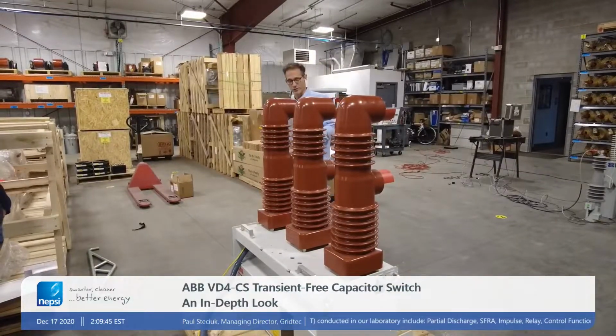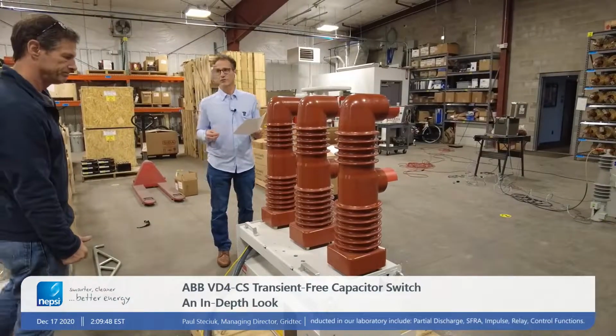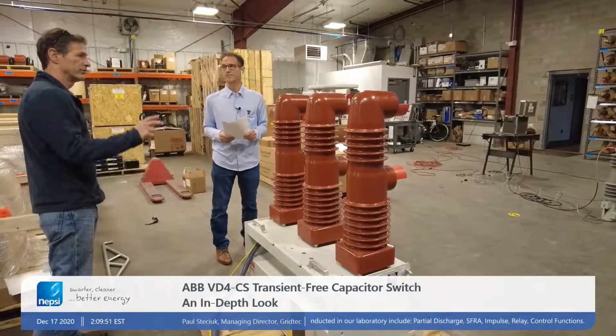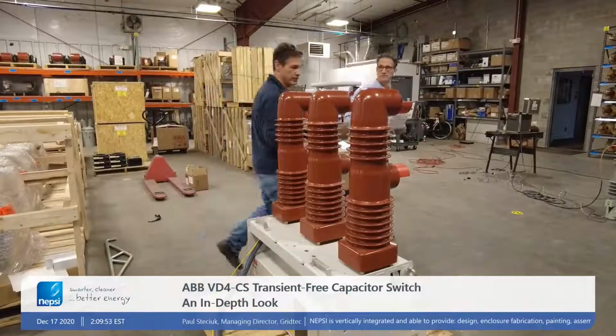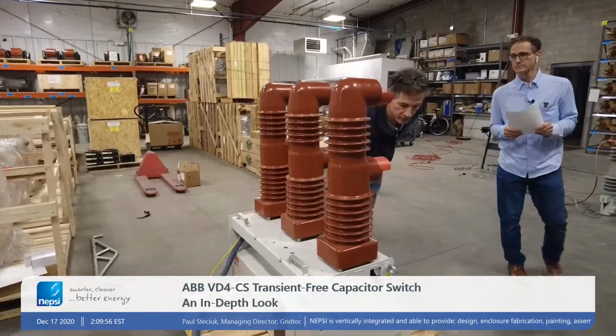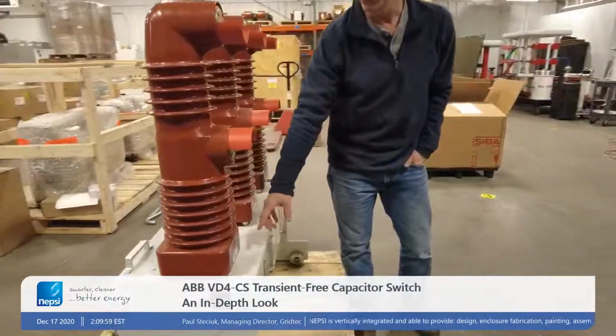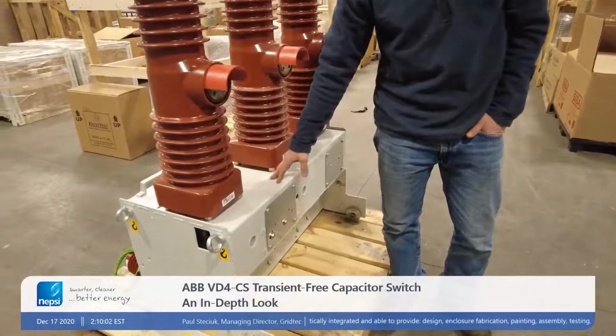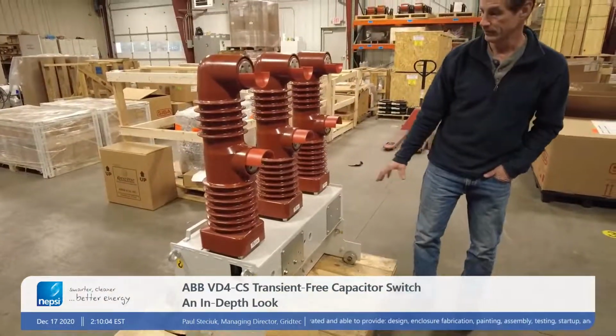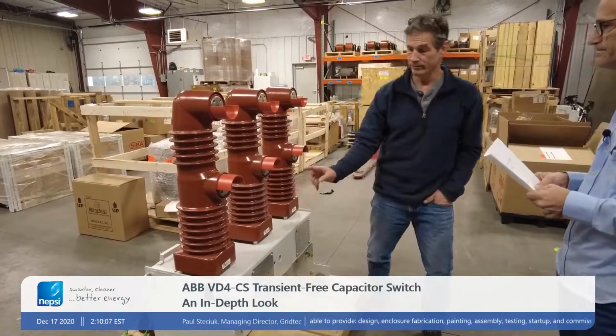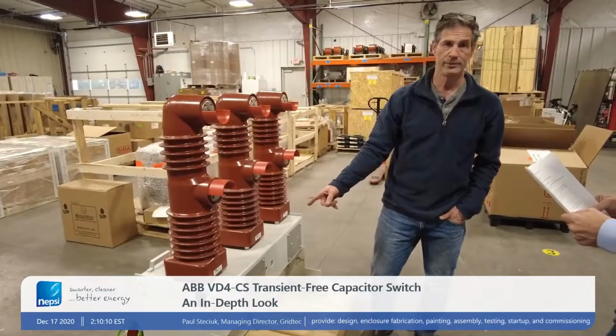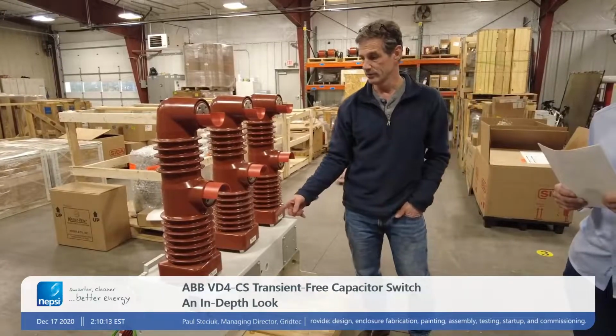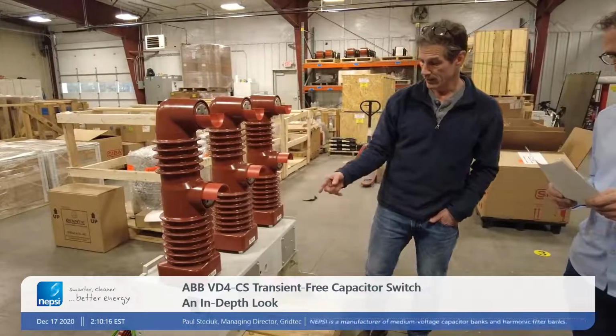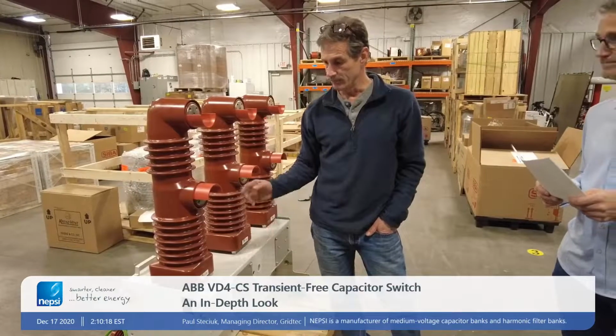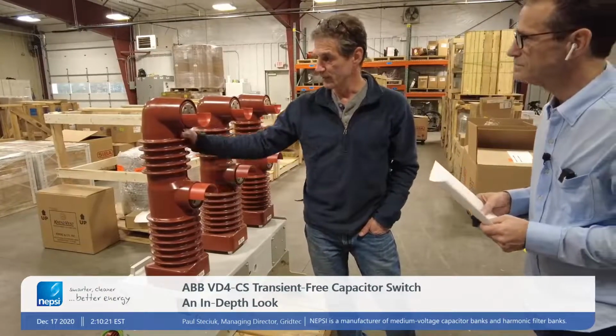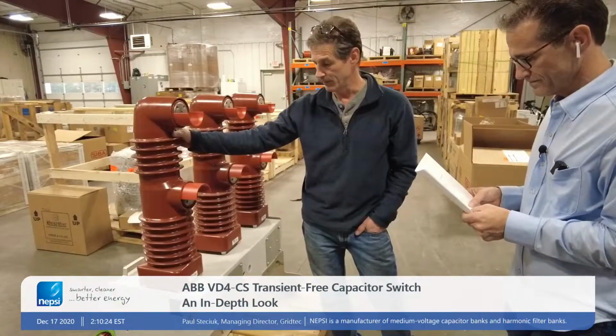So Pete, what do we do when we have cold temperature environments where temperatures can get below 0 degrees Celsius? There are two things we do. One, we install a box heater inside the mechanism with a thermostat that heats the internals. We also put in an under-temperature thermostat to monitor the temperature, just in case there's a failure of the heater circuit or the temperature gets low enough to be an issue with operation. So it's a protective mechanism.